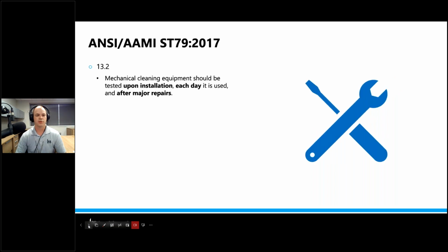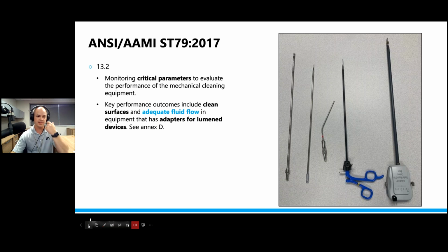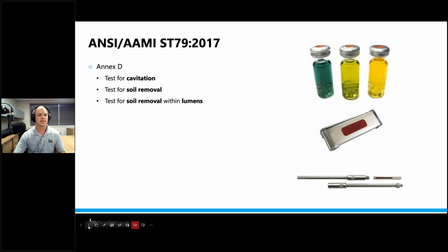Another one is it says that mechanical cleaning equipment should be tested upon installation, each day it's used, and after major repairs. So it's kind of giving us some guidance there, which will be important when we go to set up our policy and procedure for this. All right. And then another one, it says monitoring critical parameters to evaluate the performance of the mechanical cleaning equipment. And under that, it says key performance outcomes include clean surfaces and adequate fluid flow in equipment that has adapters for lumen devices. All right. And then it says to see Annex D for more clarification on that. You don't have to do that. I put it here. It says to test for cavitation, test for soil removal, and test for soil removal within lumens. And these are just ways that you can do that.